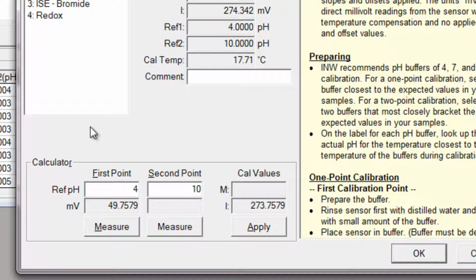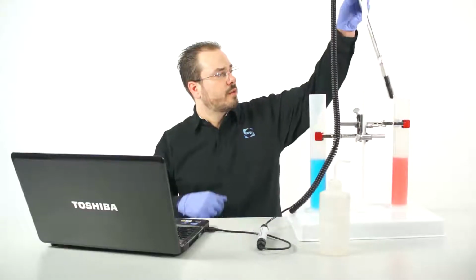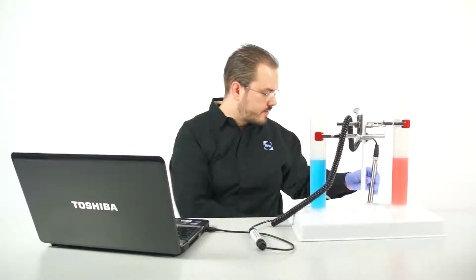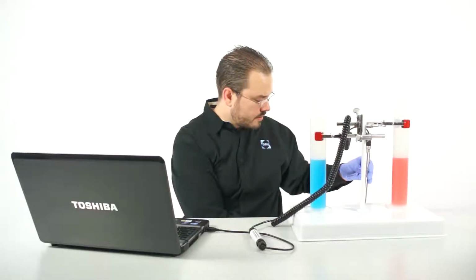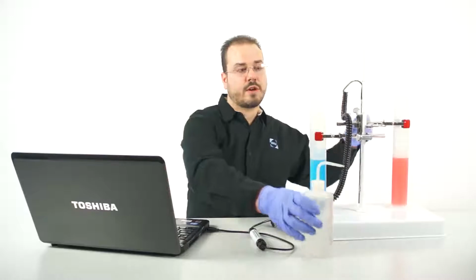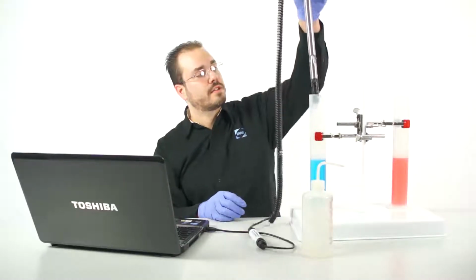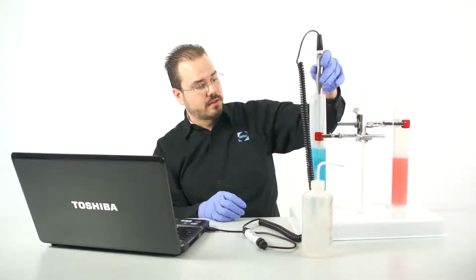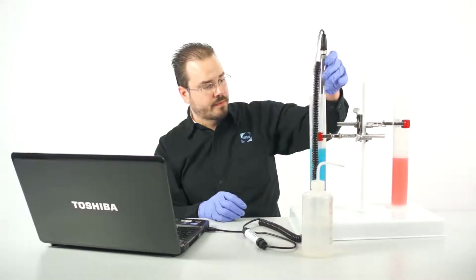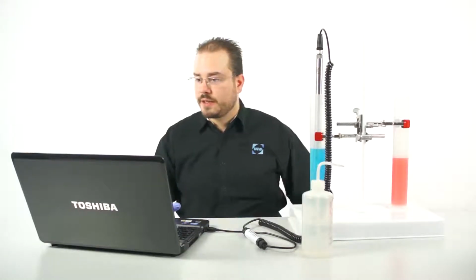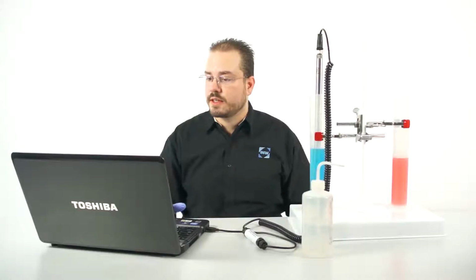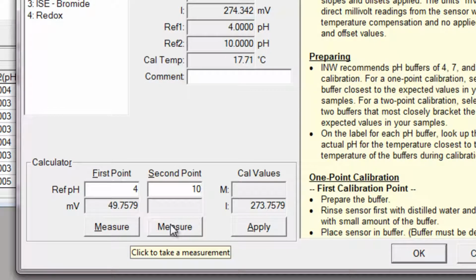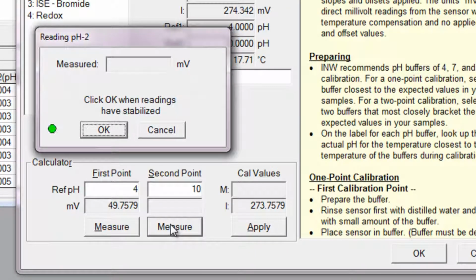We'll enter our second reference point, pH 10 in this case, and we'll move the sensor over to the second buffer. A quick rinse with DI water to avoid cross-contaminating the buffers. And then we'll be ready to take our second point readings. We'll click Measure in the calculator window for the second point. And what you'll see is a fairly quick initial drop in the millivolts into the negative range.